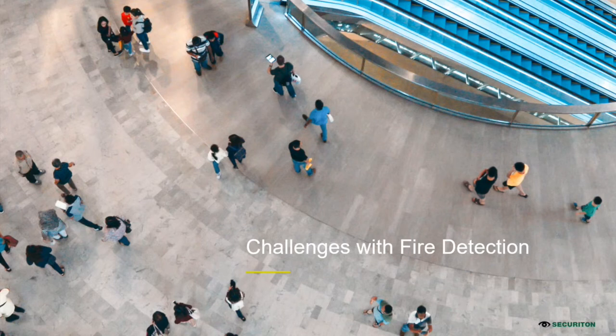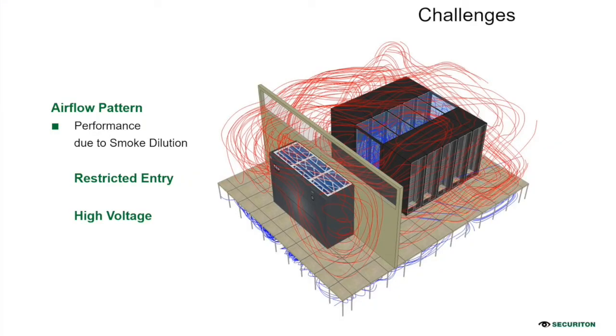Now we'll talk about some challenges with fire detection. There are three challenges which we feel are present in HVDC applications. One is the high airflow. You can relate it to the data center application. In the data center application, you also have high airflow, but in an HVDC application the airflow is 15-20 times higher than in a data center. So the chances of smoke dilution are too high.